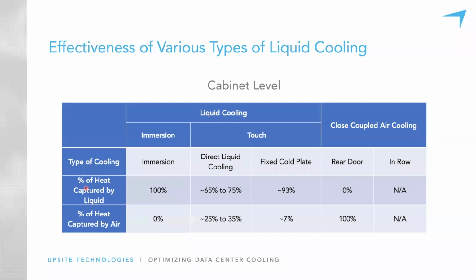So just looking at the cabinet level in this slide, this is for a cabinet that is liquid cooled, how much of the heat is picked up by liquid and how much is left to be picked up by air. So we have the different types of cooling. Immersion cooling picks up all of the heat of the equipment that is in the tank, leaving nothing needed to be picked up by air. The two forms of touch cooling: direct contact liquid cooling, somewhere around 65 to 75%, and these numbers are increasing as these solutions are refined. Somewhere around 65 to 75% of the heat is picked up by the liquid, leaving 25 to 35% of the heat to be captured by air.